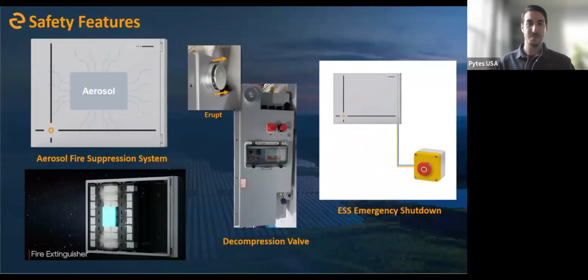So what this does is it actually opens the circuit between the battery and the inverter and ensures that there's no voltage leaving the battery itself, right? We don't have any live voltage on our inverter cables or DC bus bar. And I'll add to that, in a multi-battery system, say you've got 3 or 4 V10s connected together, you can wire your emergency push button to the primary battery, and that signal for shutdown gets cascaded to the following batteries and causes each one of the batteries in the system in a parallel configuration to all open their breakers in sequence. So again, ensuring no voltage anywhere on the DC bus or at the inverter coming from the batteries.